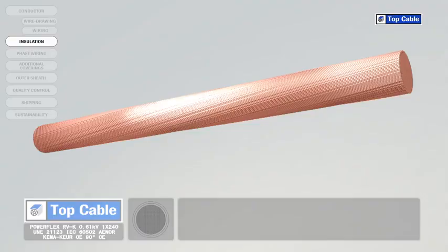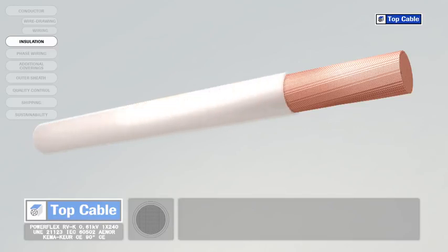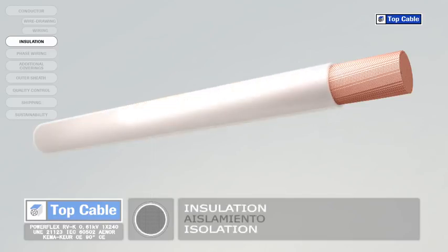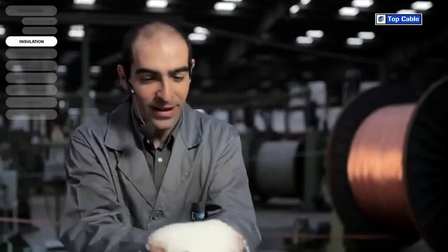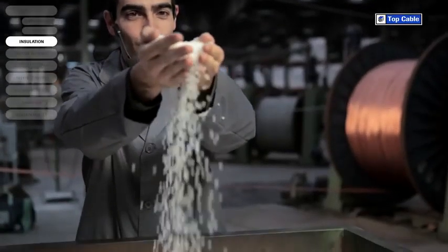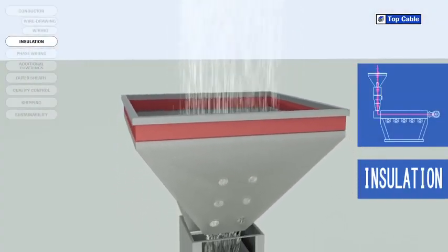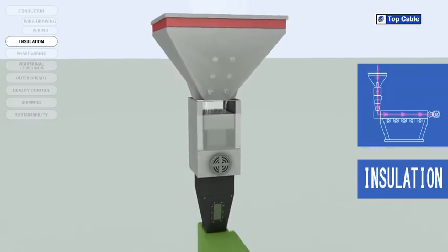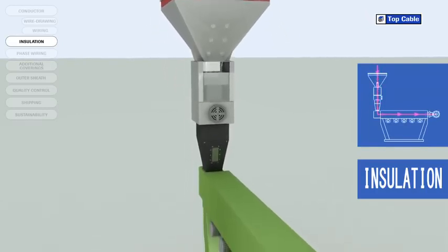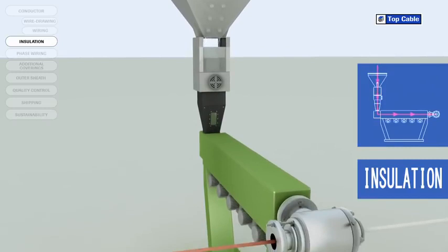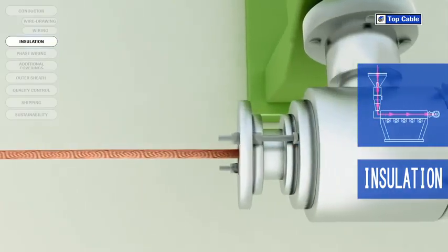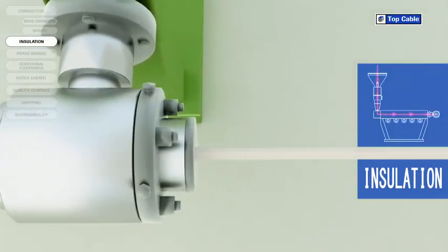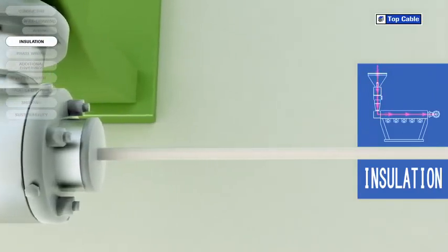The next process in the manufacture of electrical cables is the insulation. This is when we place an insulating cover over the conductor to prevent current leakages. The insulating material is added by a process of extrusion at high temperature. Several insulating materials may be used — PVC, EPR, XLPE, etc. Different insulation materials may be used depending on the characteristics of the cable required.